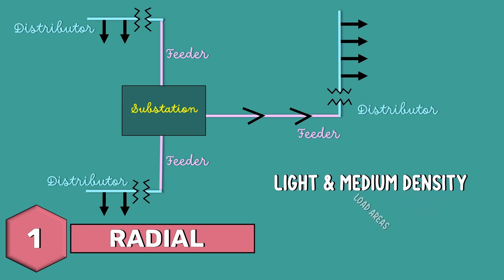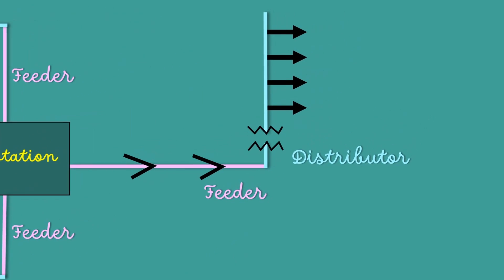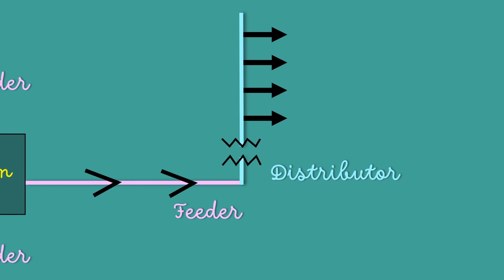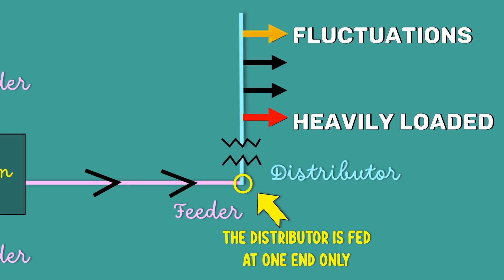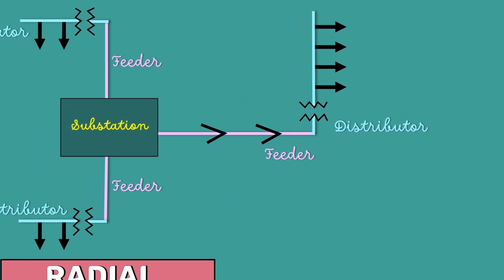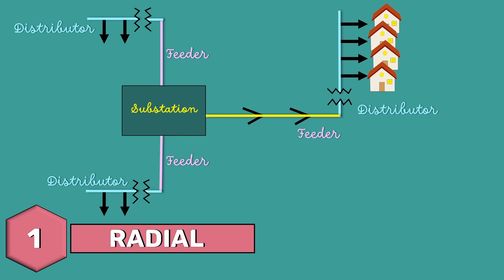This system has some drawbacks. If you look carefully, you can understand that the distributor is fed at one end only. This end of the distributor nearest to the feeding point will be heavily loaded and the consumers at the distant end of the distributor would be subjected to serious fluctuations when the load on the distributor changes. Since the consumers are dependent on a single feeder and single distributor, any fault on the feeder or distributor cuts off supply to the consumers connected to the distributor.